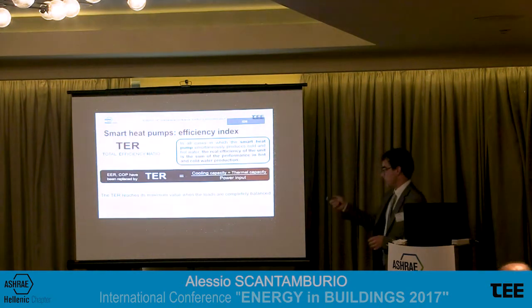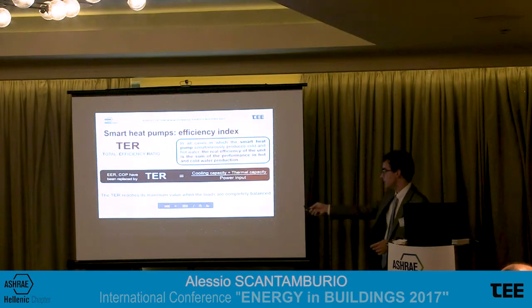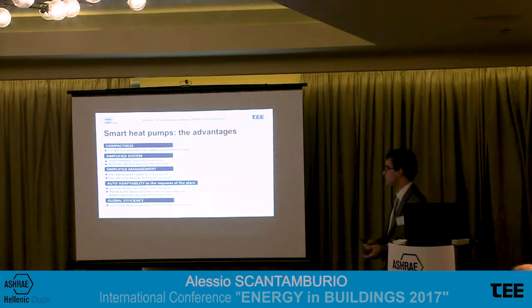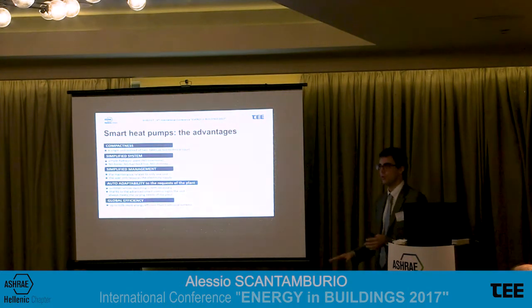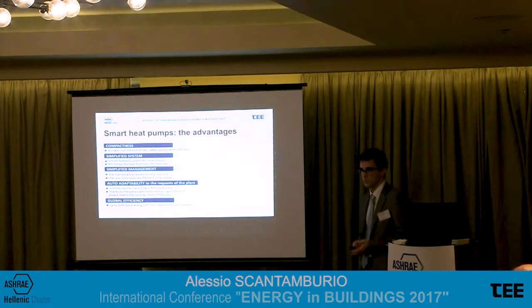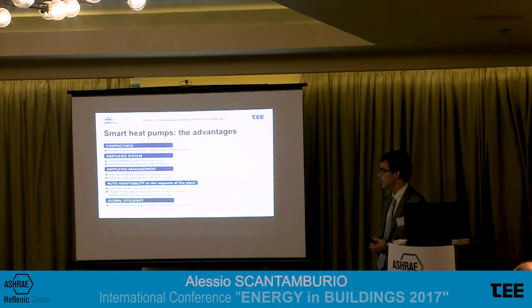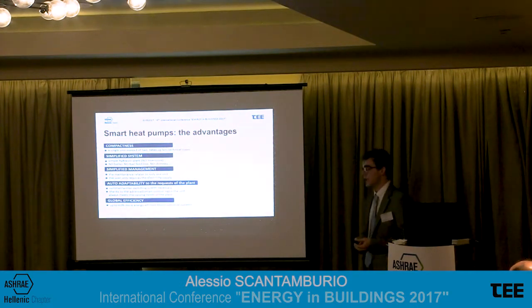Okay. Like already explained, the TER, total efficiency ratio, is the ratio between the sum of cooling capacity and thermal capacity divided by the power input. So just to resume the main advantages of using this solution in a 4-pipe building, so in a building that requires hot water and cold water at the same time: the unit is more compact. We don't need the gas boilers, so of course we take less technical room. The system is simplified because we don't have to manage hydraulic inversion on the plant, and we don't need all the stuff related to the boiler, so fuel lines, chimneys, and so on.